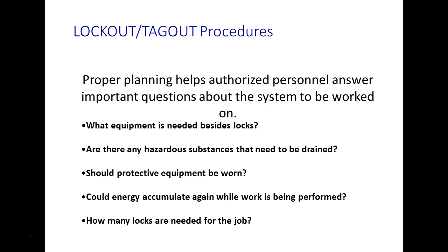The key factor in telling you when you need to do what: if you're going to work on it, you lock and tag. If you're going to troubleshoot on it, then we don't lock it. That makes sense—if you're going to get your hands in that thing, then we need to lock and tag. So anytime you replace parts, even a lot of times during preventive maintenance like greasing, our robots need to be greased. So if you're out there on that robot greasing it, and it's a big robot, then you need to lock and tag, unless they come up with another method of preventing that thing from moving.